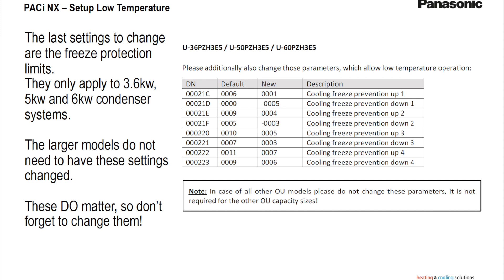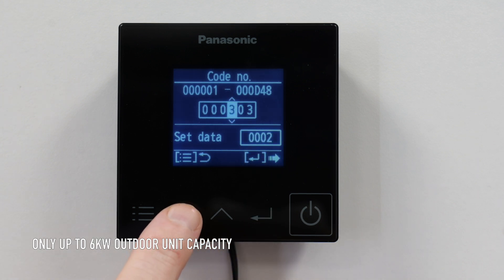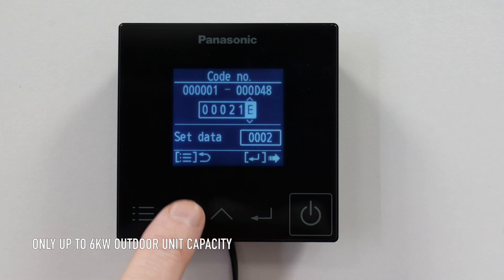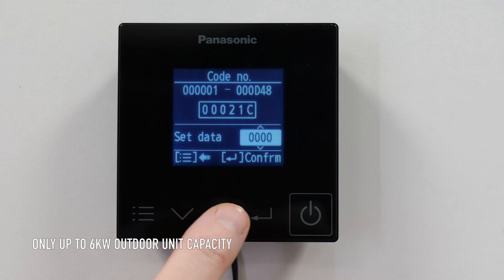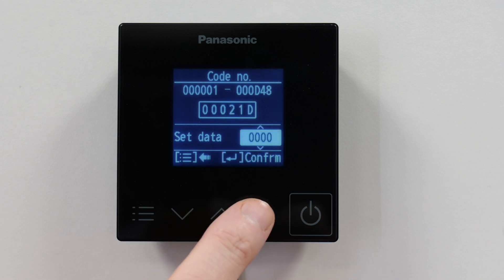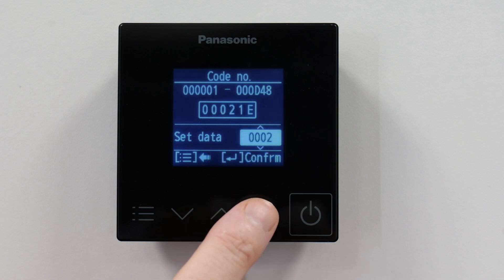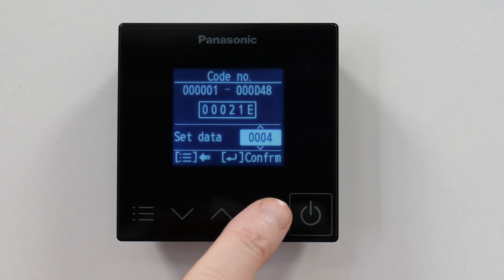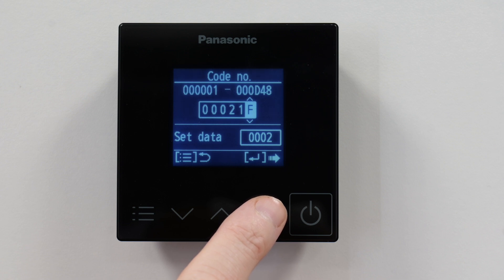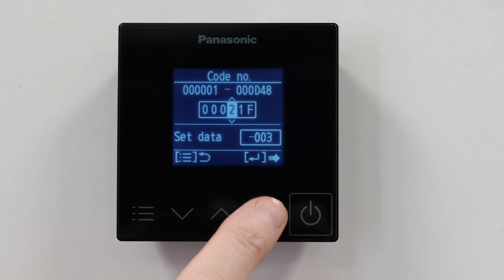Once we've done that, we're going to need to set the frost protection settings. The first setting we change is code 21C — change that on the controller and set it to 00001. Then code 21D, set that one to minus 005. Code 21E, set that to 0004. Code 21F, set that to minus 003.